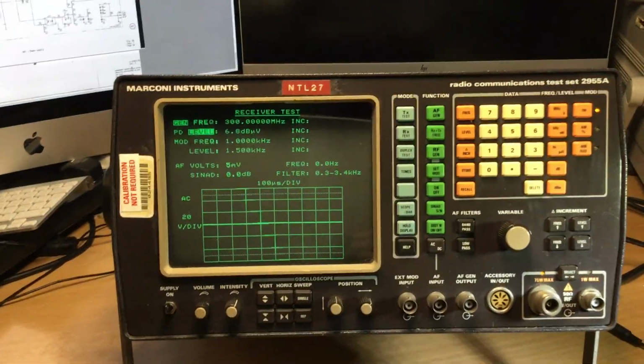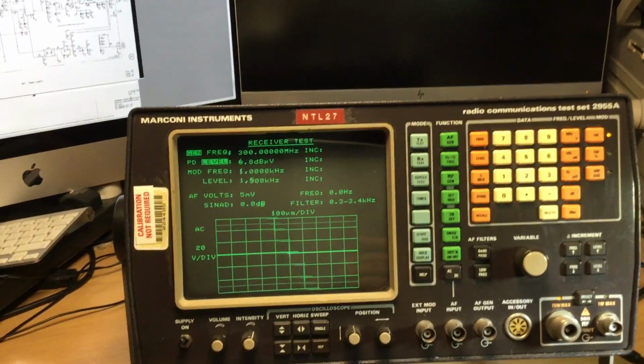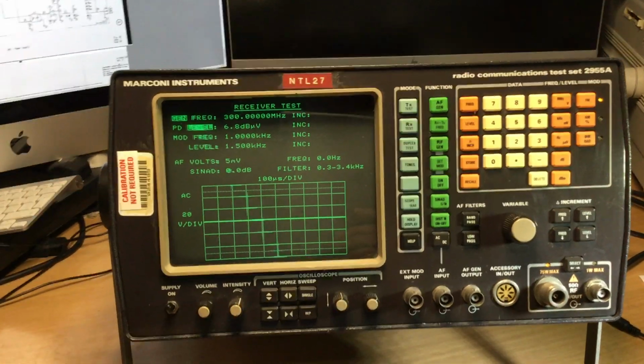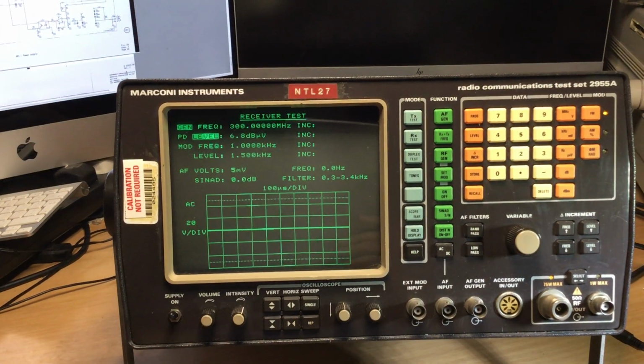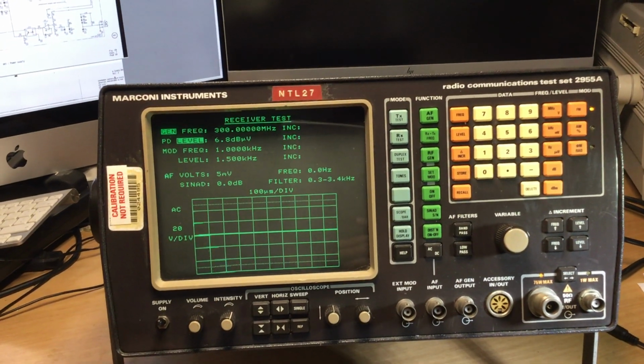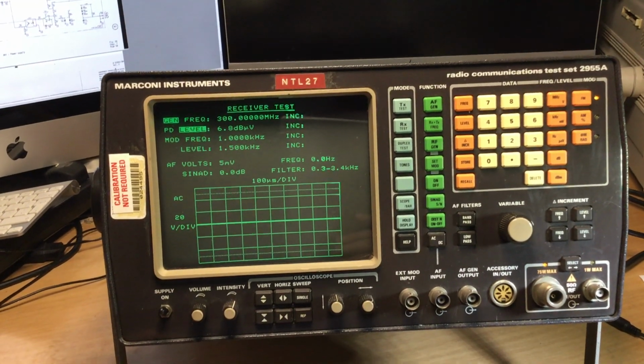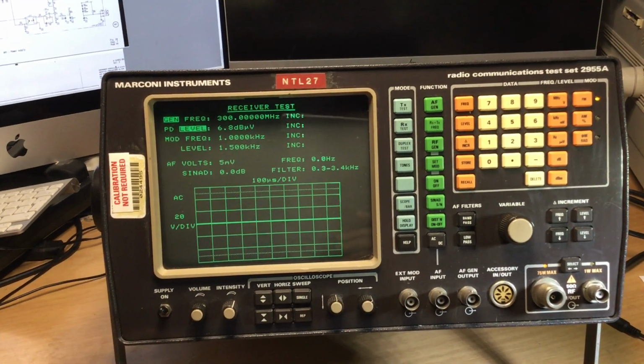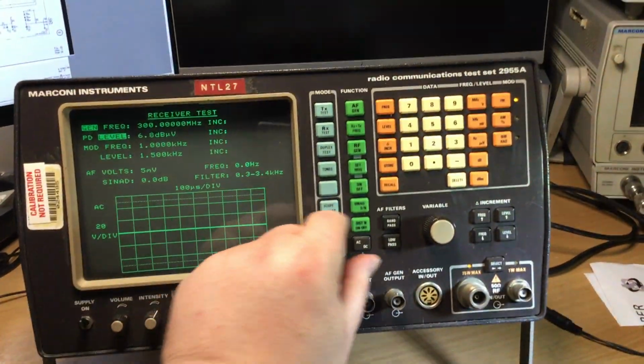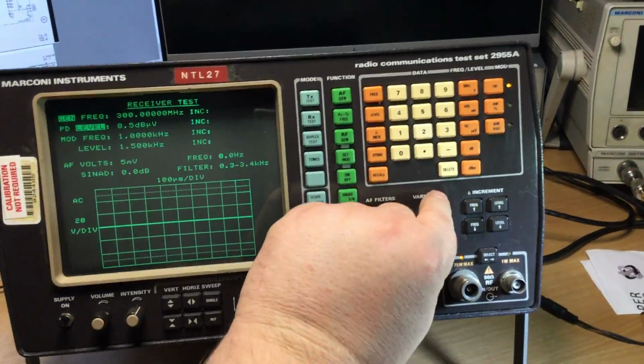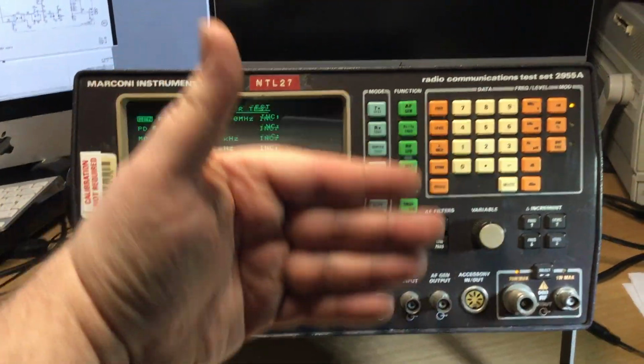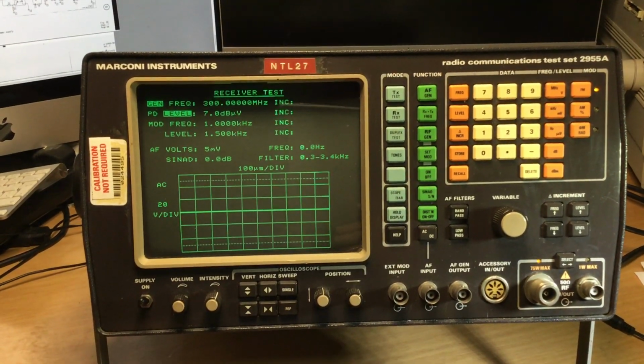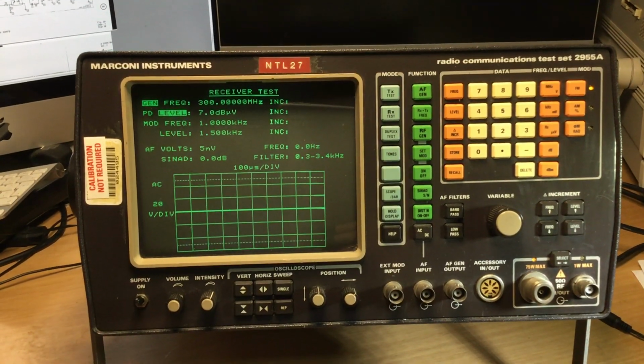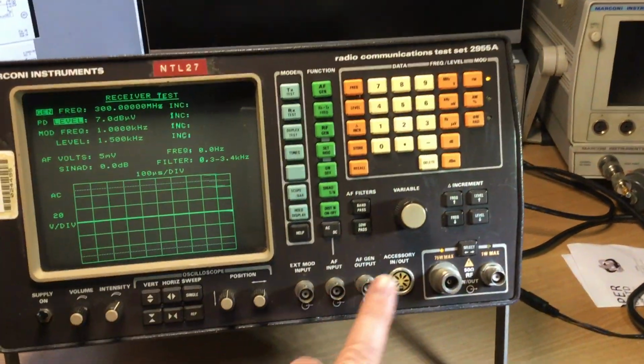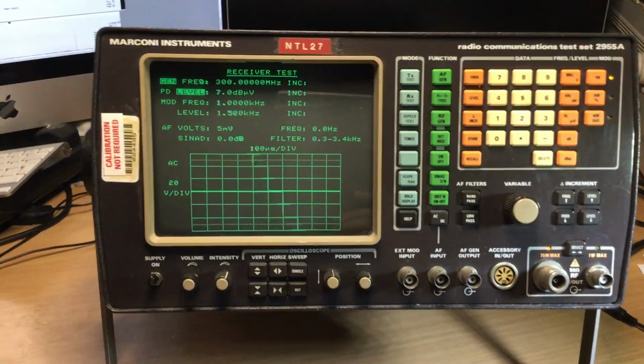And obviously the digital to analog conversion DAC value levels linked to that level, if you like, within the memory has to be stored in memory, and then that DAC value is stored in memory, so that when we dial up on the front a level, or we adjust this, it recalls that level from memory at that particular frequency, and it adjusts the attenuation precisely so that it gives the correct output from these two ports. Otherwise it'll be out of spec.